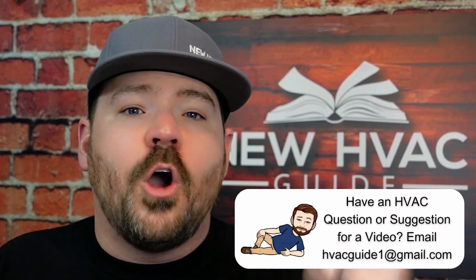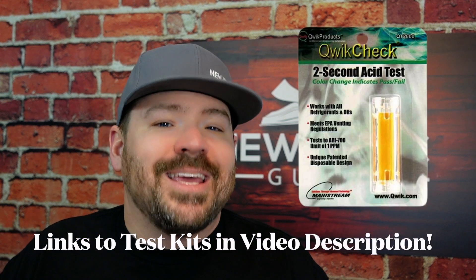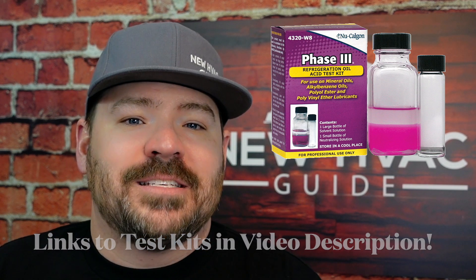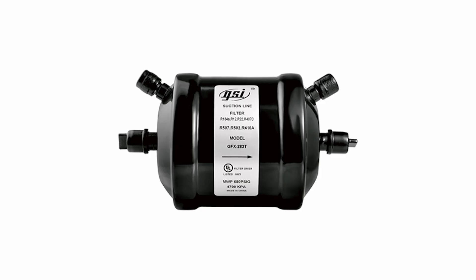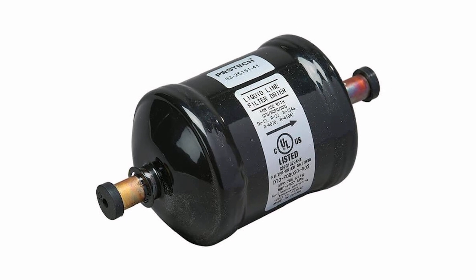What do you do if you're the homeowner who has had some issues or wants to get in front of this? This is something you can literally have tested. You can have a heating and air company test the oil in that system — there are little kits, they're not free but not that expensive either. They can test the oil and let you know if there is acid present. And one step further: if you find out there is acidity in that system, there are products that can neutralize that acid. When you hear of guys installing multiple compressors in a system, they need to be brazing with nitrogen, triple evacuating, maybe installing a suction line filter dryer if needed, definitely replacing that liquid line filter dryer anytime the system has been opened up, and testing for this acid — doing something proactive to inhibit this from continuing to be an issue.